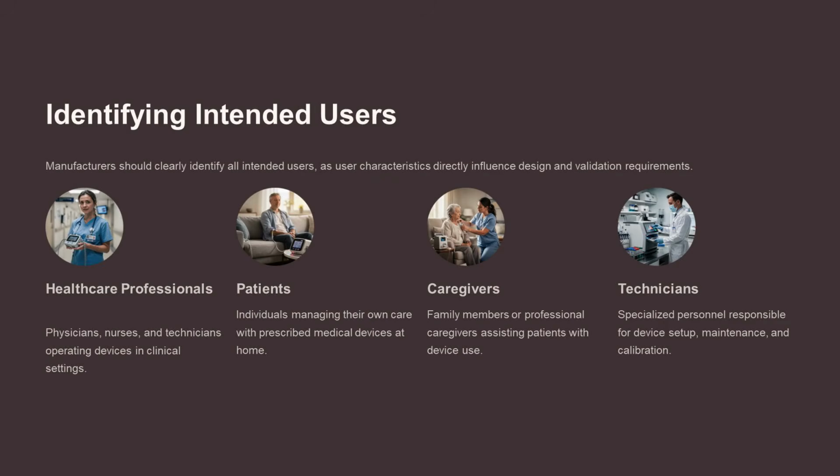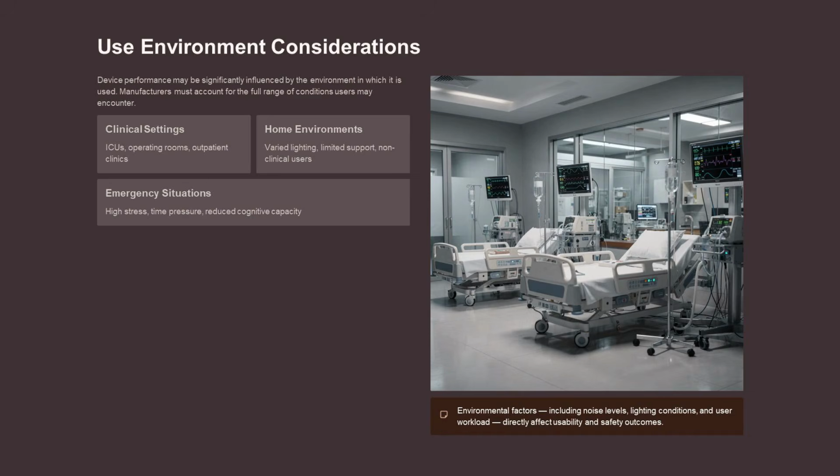Identifying intended users is crucial as user characteristics influence design and validation requirements. This includes healthcare professionals, patients, caregivers, and technicians. Device performance is influenced by the environment, including clinical settings, home environments, and emergency situations. Manufacturers must consider these factors for safety and outcomes.